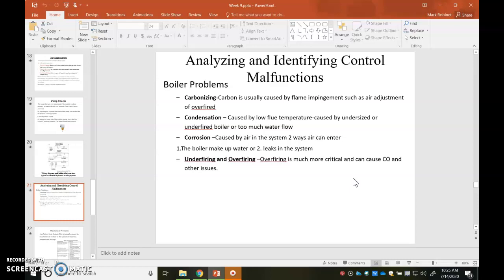It does a couple things. It insulates the boiler so that you get no heat transfer. So the more carbon you make, the longer the boiler runs, the more carbon you make. So it's a really detrimental thing to a boiler. So that's why with boilers, you want to make sure that they're nice and clean and that you have a good heat transfer.